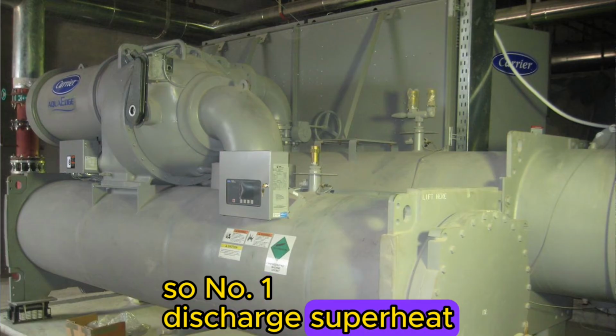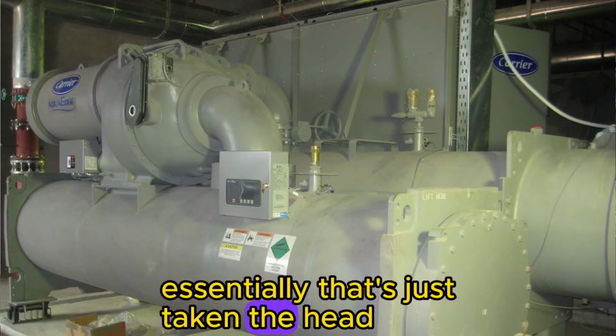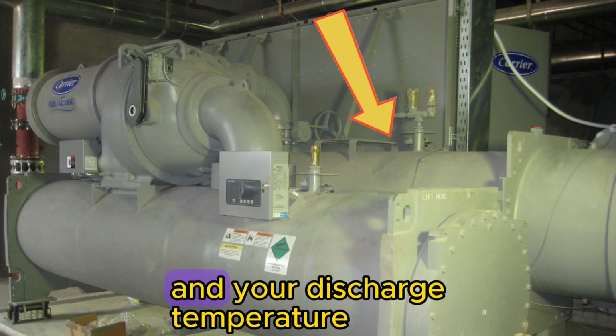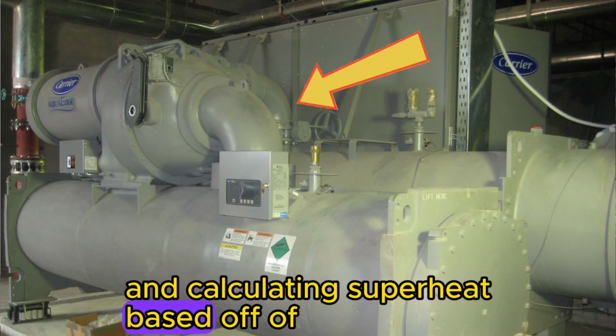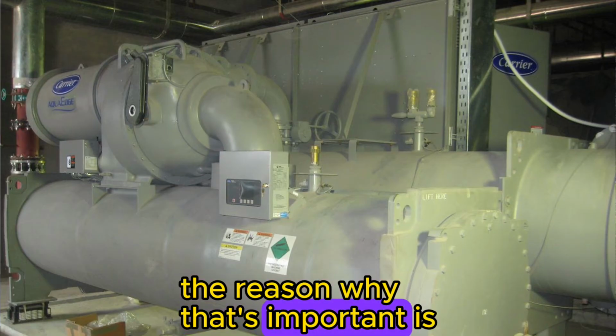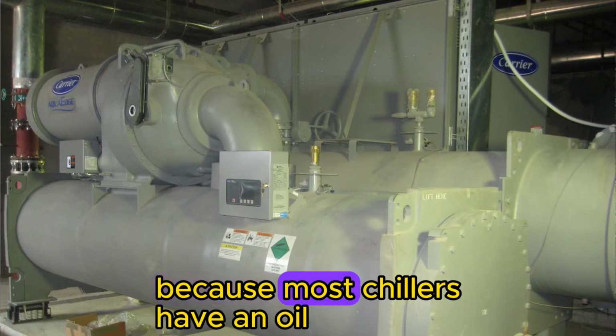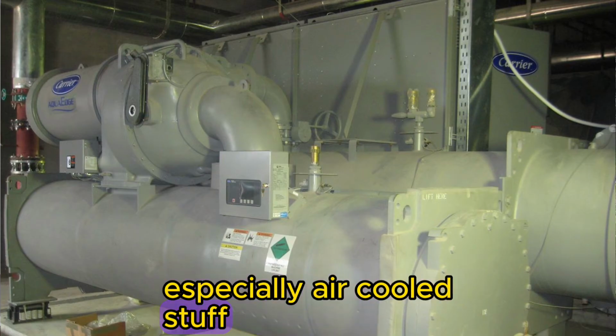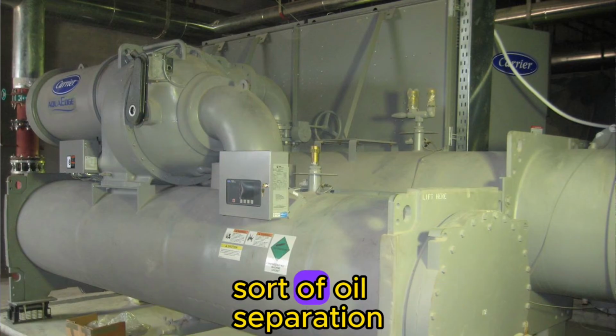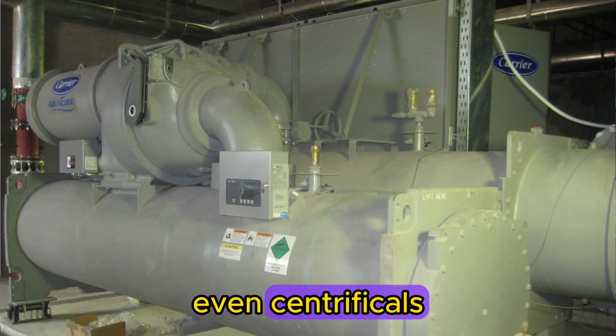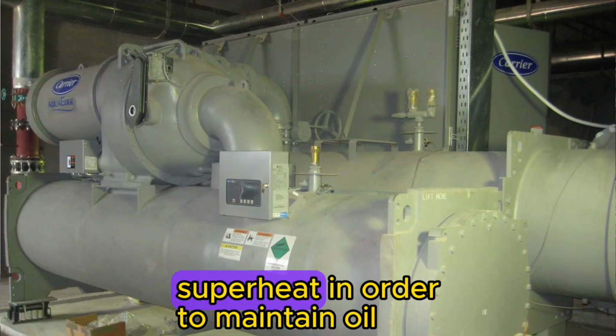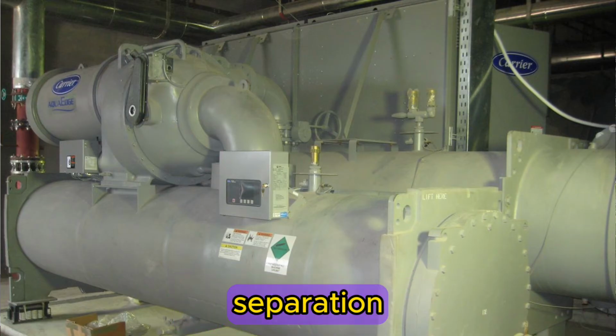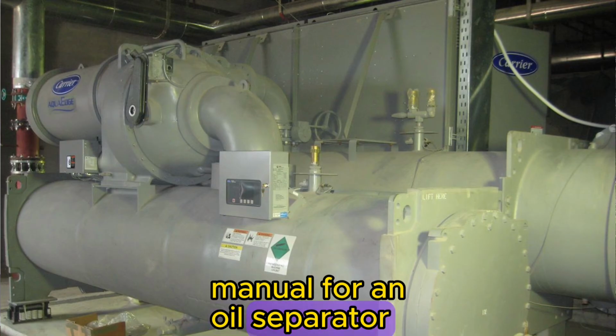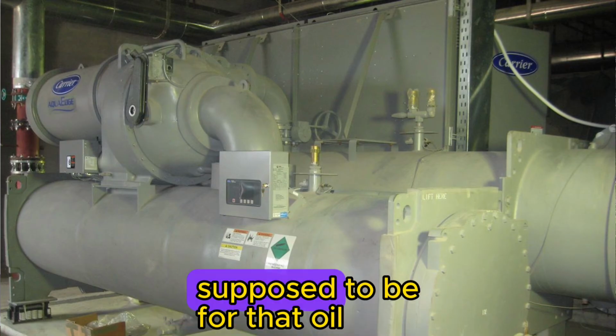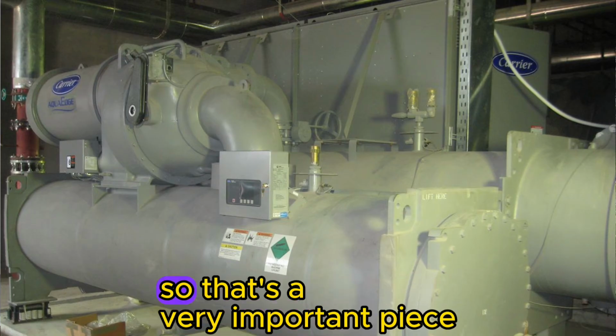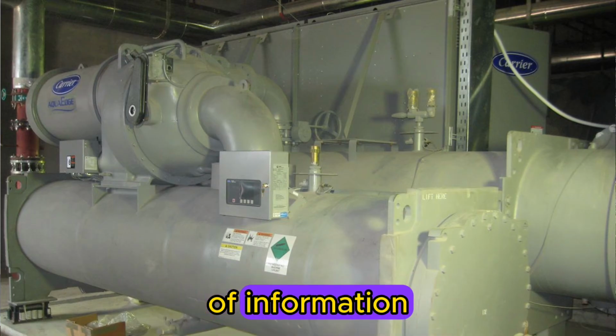So number 1, discharge superheat. Essentially, that's taking the head pressure and your discharge temperature and calculating superheat based off of that. The reason that's important is because most chillers have an oil separator, especially air-cooled stuff. Even centrifugals require a certain level of discharge superheat in order to maintain oil separation. So if you look in the manual for an oil separator, it'll tell you what the design discharge superheat is supposed to be for that oil separator to work properly. That's a very important piece of information.